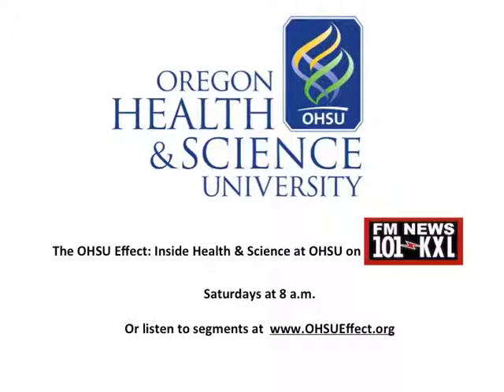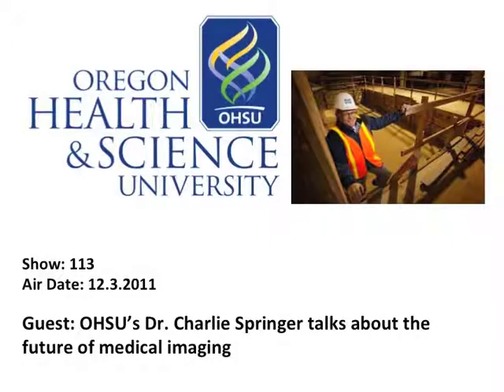Tell us about it. One of the ways that you characterize MRI instruments is by the strength of the magnetic field. As most listeners know, magnetic resonance imaging involves the use of a large magnet, and you can characterize the strength of the magnetic field in the unit called Tesla. So we have a 7 Tesla magnet that's a size for human subjects, and there are very few of those in the world. And we have a smaller instrument for animal model studies that is 12 Tesla, which is a very high magnetic field.